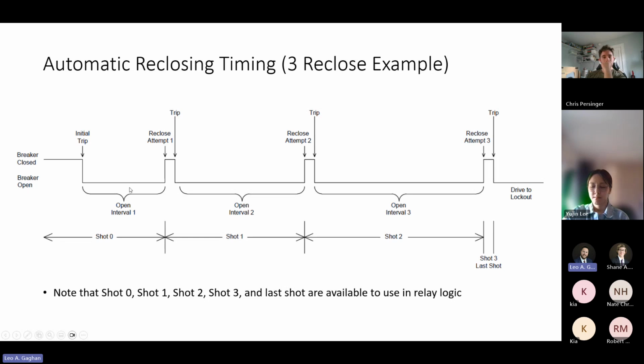So the breaker can be open for a period of time, the open interval, and then we're going to have our reclose attempt. That's going to be our first shot right there. That's the term shot. It's our first reclose attempt. Everything up until there, the relay is going to be in shot 0. Well, let's say it was a permanent fault, and we pretty much immediately trip back out. Well, what's going to happen then? We trip, the breaker opens, and we start what's called open interval 2. Again, we can define that. Maybe we want it to be a little bit longer than open interval 1 was. Let's say, 20 seconds. Well, the breaker will stay open for those 20 seconds, and then it will have reclose attempt 2 or shot 2, and the breaker will close again.